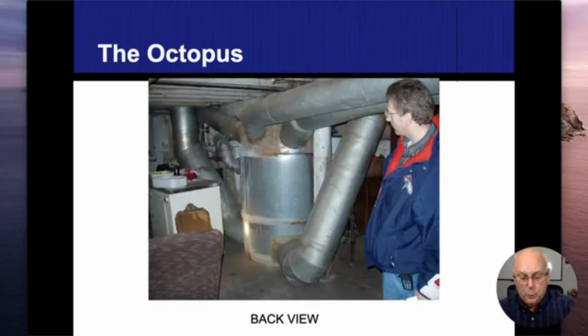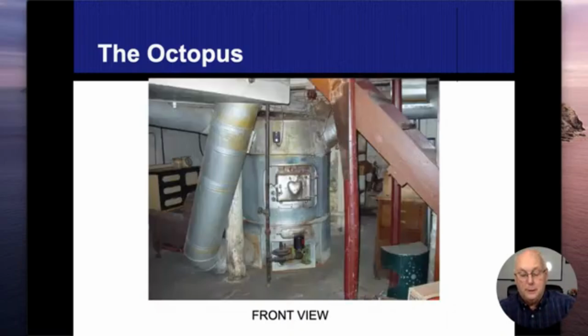So the returns. So this is a return. Back here is a return. These things are supposed to be 3 times as big as whatever the supplies are. So these are our supplies. Typically these are going to be 8-inch ducts that go to the different rooms, and these would be 2-foot returns that come back. Again, no filter, no fan, or nothing else. Over here is going to be my vent connector. And if I follow that, that's going to go to the chimney. We go back to the front of this.